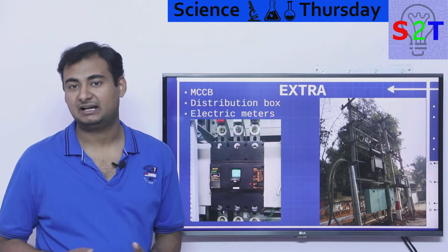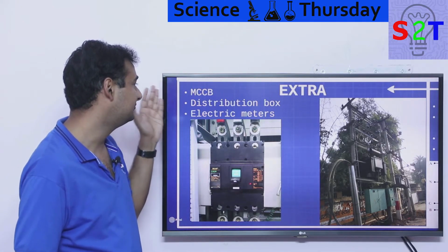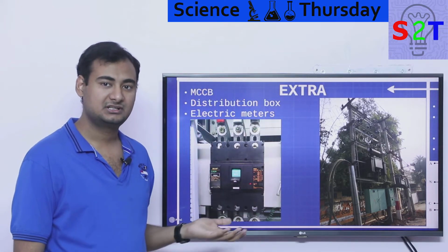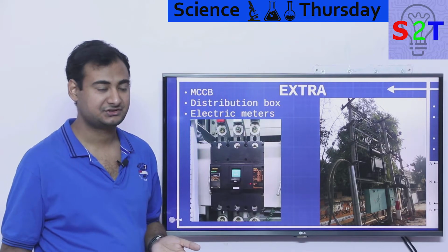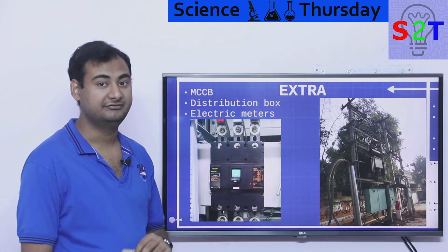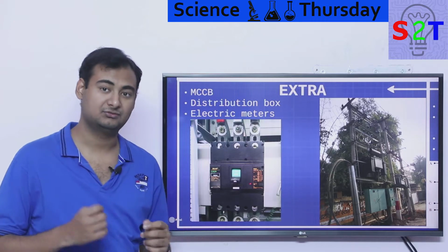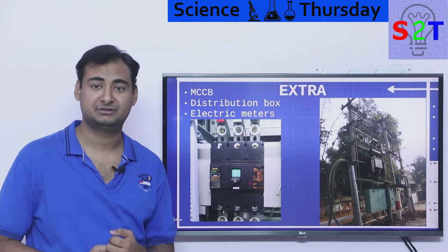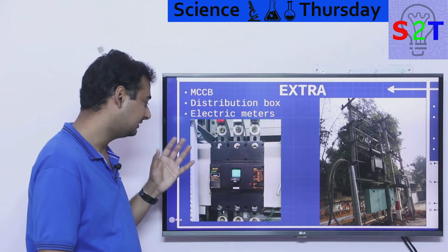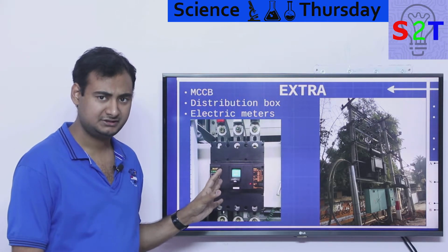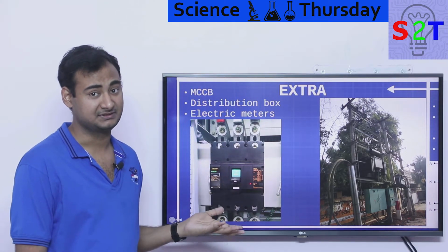Now there are certain extra add-ons you can see around. Sometimes you see an MCCB - basically a bigger brother of the MCB, miniature circuit breaker, but these are designed for very high amperage. I already told you, if you want a 500 ampere fuse, it's very expensive. So generally the MCCB is a newer development - it's not that it didn't used to exist, it was just very expensive, now it's cheap.